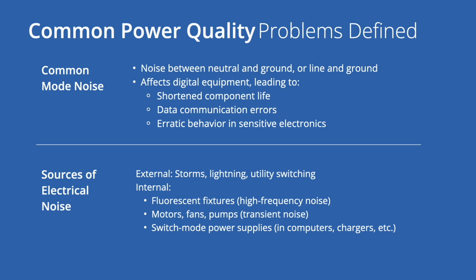Common mode noise: noise between neutral and ground or line and ground. Affects digital equipment, leading to shortened component life, data communication errors, erratic behavior in sensitive electronics. Sources of electrical noise: external, storms, lightning, utility switching. Internal, fluorescent fixtures, high frequency noise. Motors, fans, pumps, transient noise. Switch mode power supplies in computers, chargers, etc.